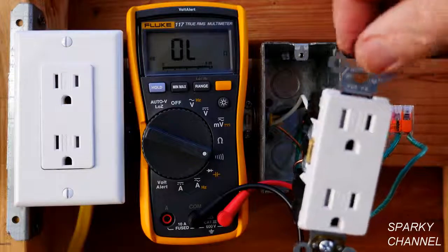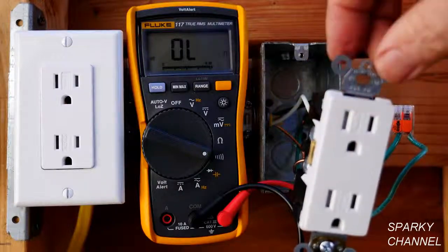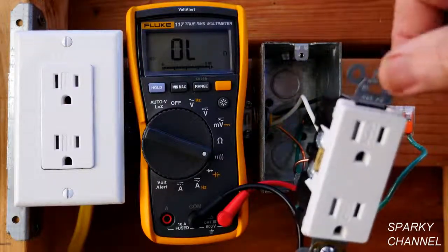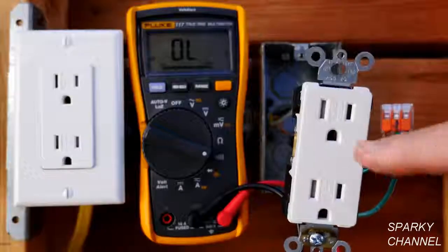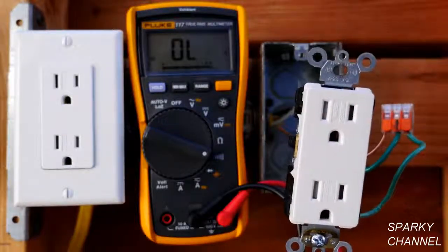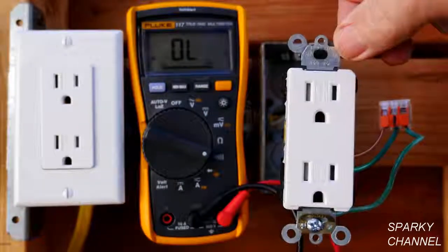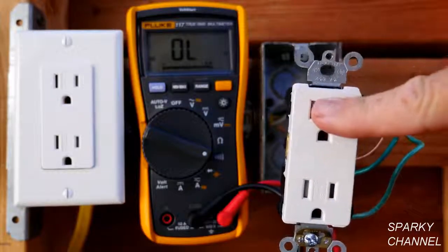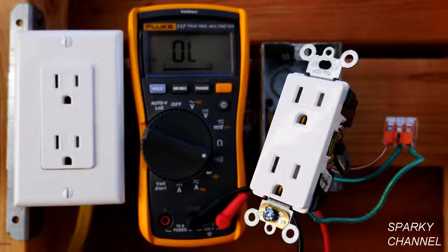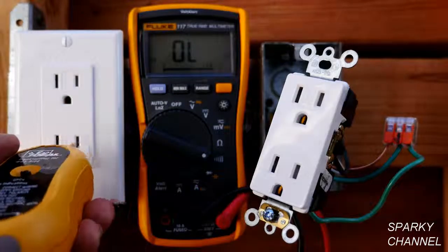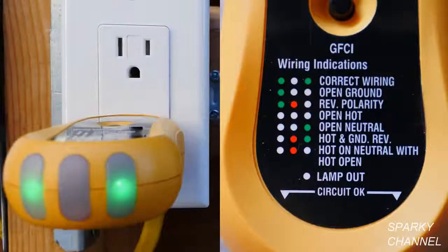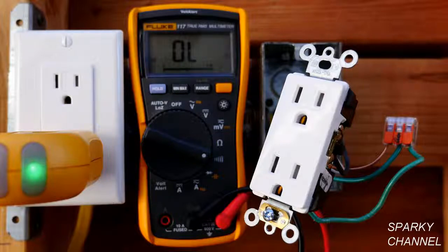I want to point out one thing. There's just one cable coming to this box, so that means that this is the end of the run box. And what we're going to need to do is look at the next receptacle upstream, because that's where we may find our open neutral problem. I have turned the circuit breaker on just briefly for this test. I'm going to go ahead and plug this in and see if we get two lights on either side. And if you look at the index, it says correct wiring. So this one is wired correctly. So the box on the left shows correct wiring. The box on the right has shown open neutral.